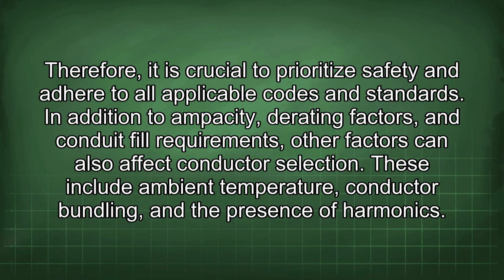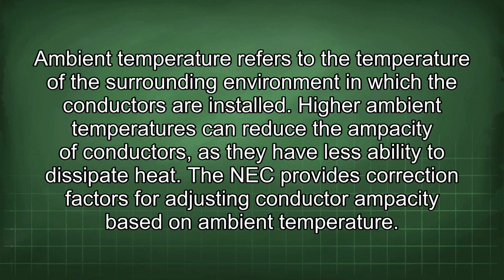In addition to ampacity, derating factors, and conduit fill requirements, other factors can also affect conductor selection. These include ambient temperature, conductor bundling, and the presence of harmonics. Ambient temperature refers to the temperature of the surrounding environment in which the conductors are installed. Higher ambient temperatures can reduce the ampacity of conductors, as they have less ability to dissipate heat. The NEC provides correction factors for adjusting conductor ampacity based on ambient temperature.